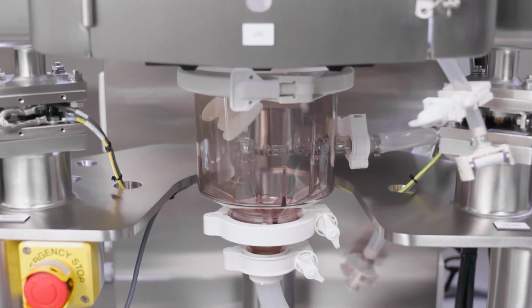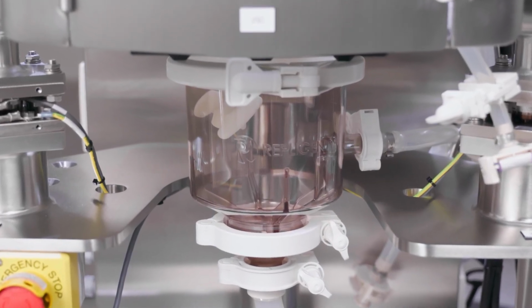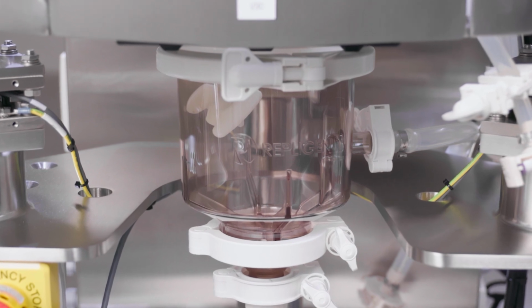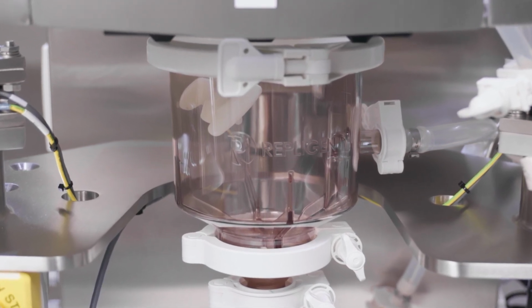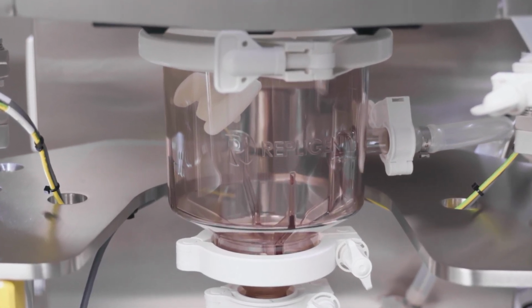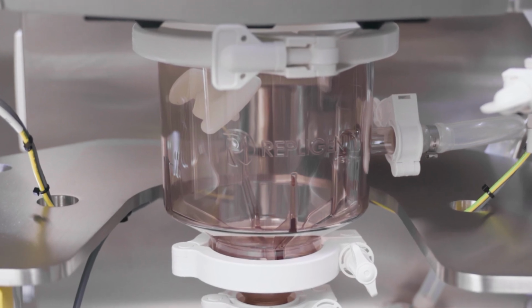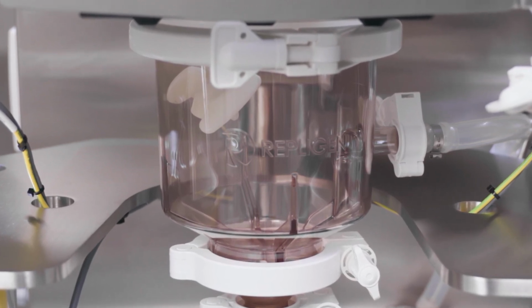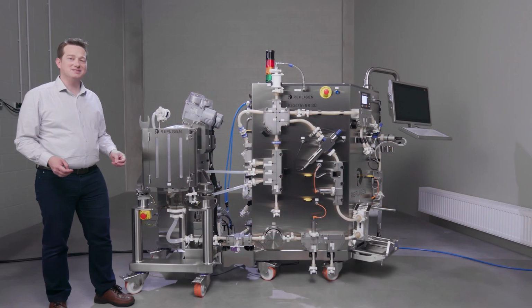Our unique sump design provides active mixing all the way down to 2.5 liters and keeps the lowest return line completely covered all the way down to 1.5 liters. The sump and its outlet are specifically designed to allow you to maintain high flow rates even at low minimum working volumes, making your TFF process even more efficient. Now let's walk through the process flow on this system.